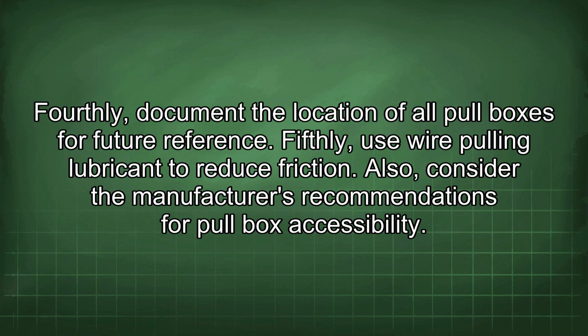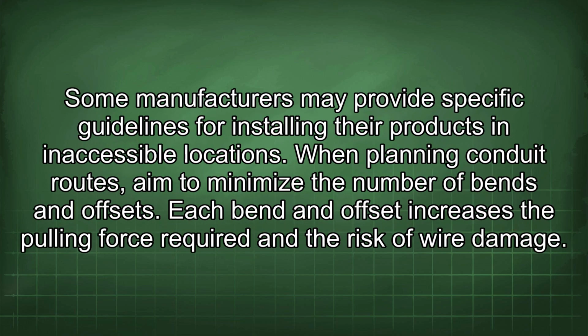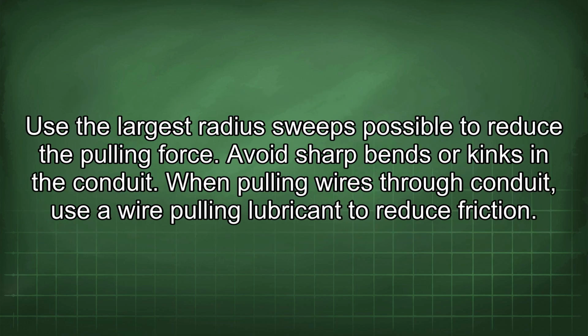Also, consider the manufacturer's recommendations for pull box accessibility. Some manufacturers may provide specific guidelines for installing their products in inaccessible locations. When planning conduit routes, aim to minimize the number of bends and offsets. Each bend and offset increases the pulling force required and the risk of wire damage. Use the largest radius sweeps possible to reduce the pulling force. Avoid sharp bends or kinks in the conduit.